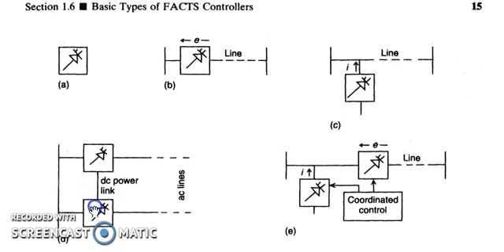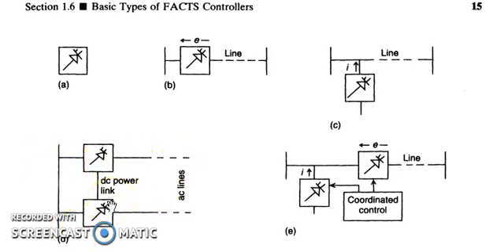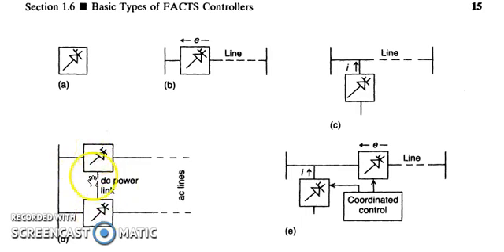Coming to figure D, we have a series-series controller where one controller is connected in series with one transmission line and another is connected in series with a second transmission line, and both are interconnected by a DC power link. This means there can be actual power transfer between the two transmission lines via the DC link — it is not just a control signal line but an actual power link. This allows control of power flow between different transmission lines.